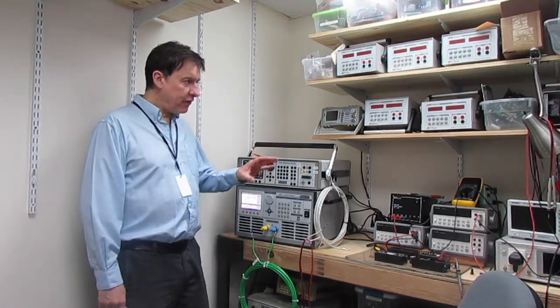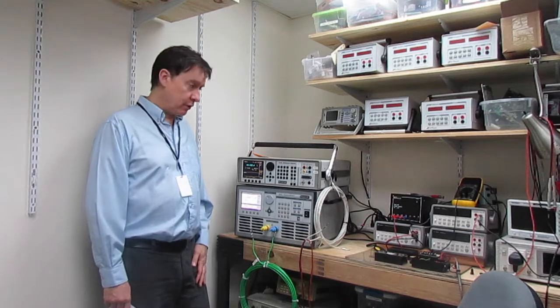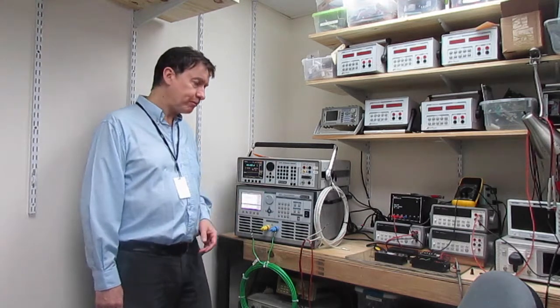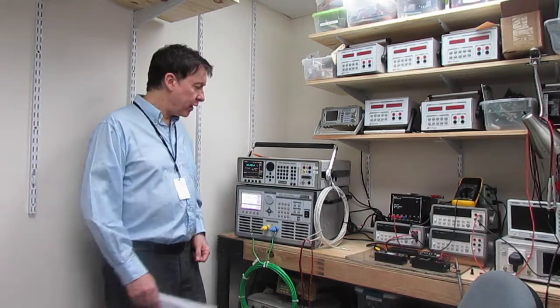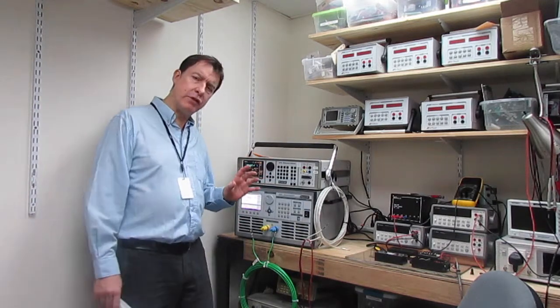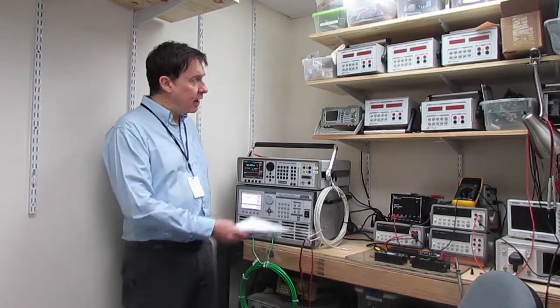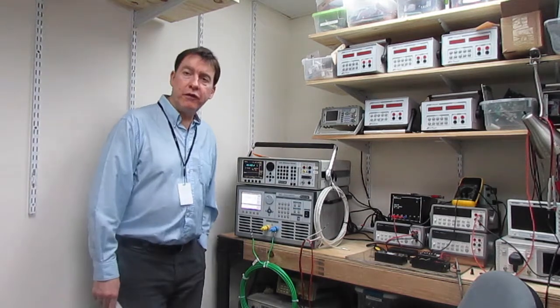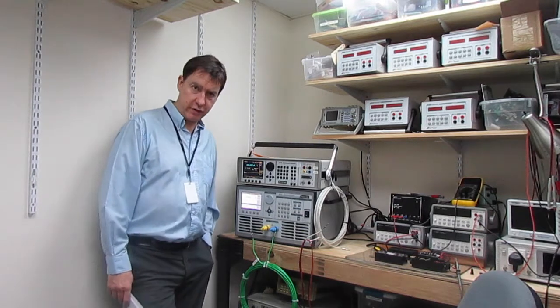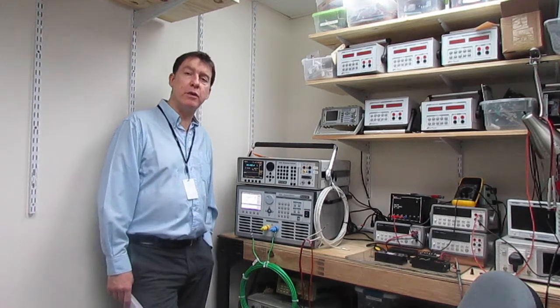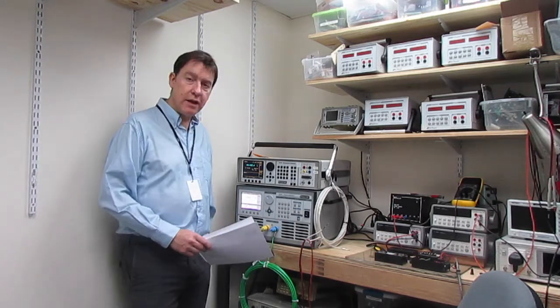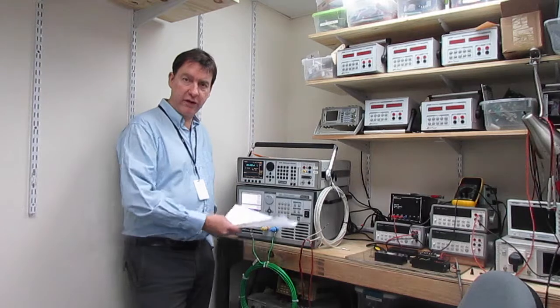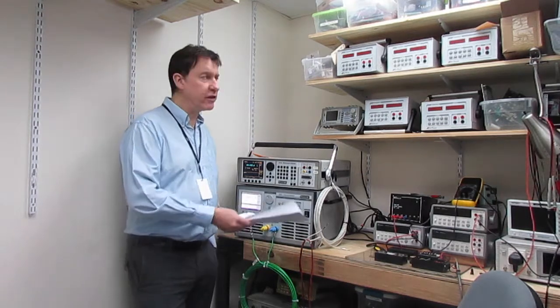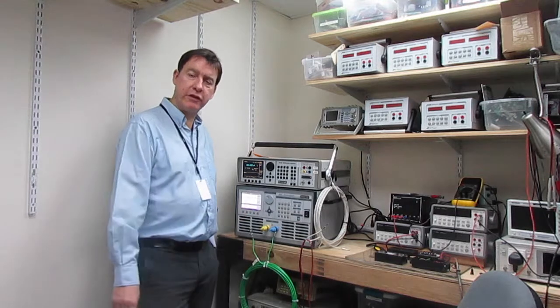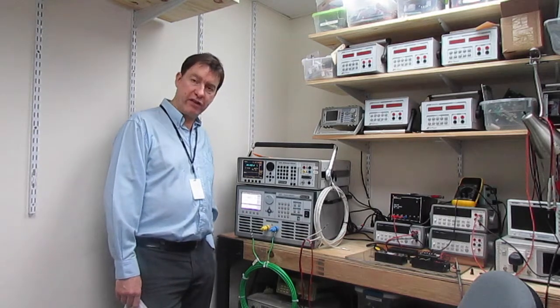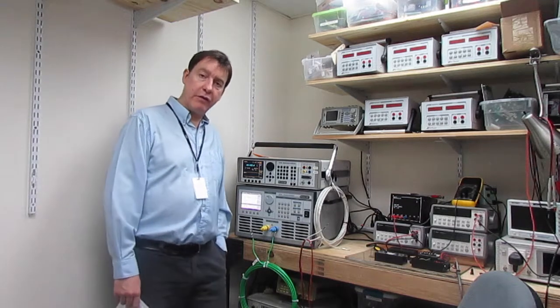Bearing in mind that we have several standards within the actual laboratory here, which are standard shunts, high accuracy DMMs, so we can verify this on a monthly basis just to make sure that it is performing as we'd expect. And as you can see, Powertek is well known for making precision phase meters, which measure to like 0.01 of a degree, which is 10 millidegrees. So we are very able to verify the phase performance. So in addition to the yearly calibration cycle, we're constantly monitoring our calibrators just to make sure that we know that they're working within spec and giving a high degree of confidence.